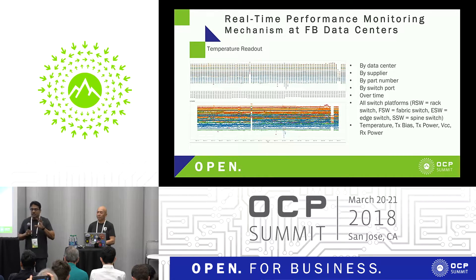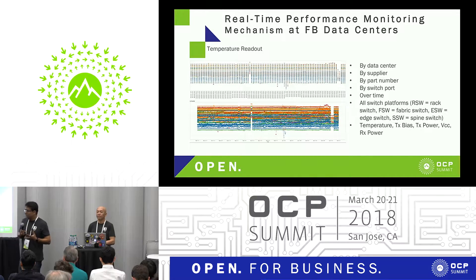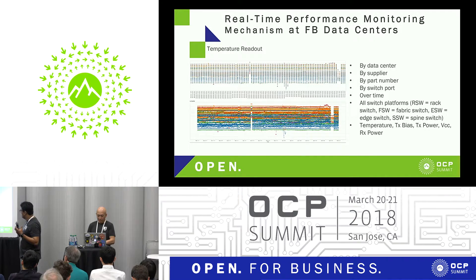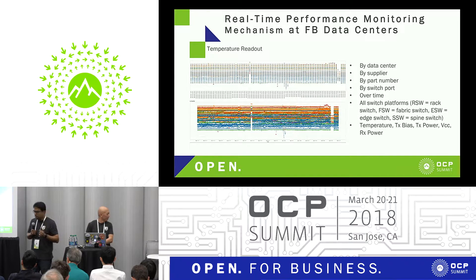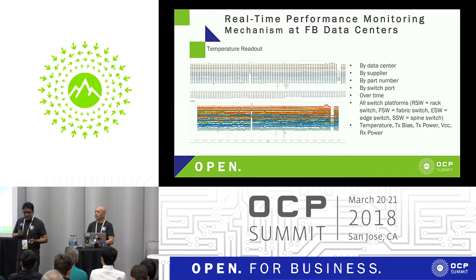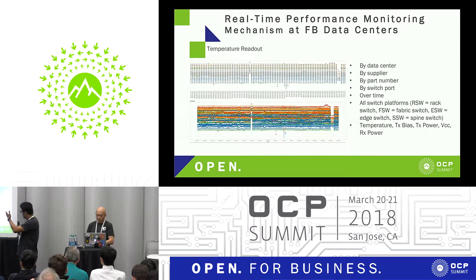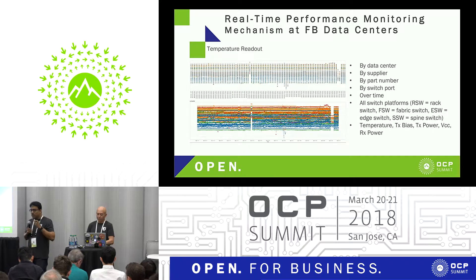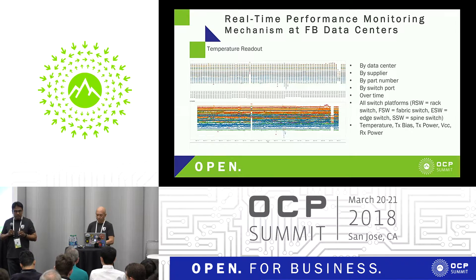Many teams worked together to understand the data collection process in real time. What we have built is a tool which pulls data through I2C. We can use that I2C feature in optical modules and pull real-time data like temperature, bias current, and also optical power — organized by data center, by supplier, by part number. We get all this information in real time from the data center.